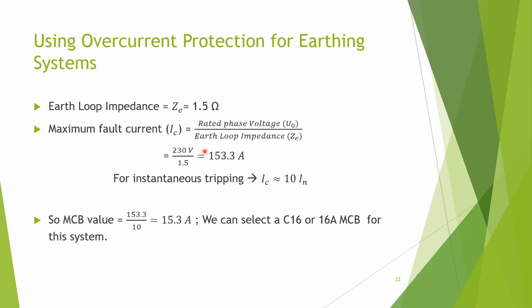And so in this case, our current is 153.3 amperes. So to select an overcurrent protection device for earth faults, we are going to divide this value by 10. 153.3 divided by 10 is 15.3, and we are going to select a 16 ampere breaker, because 16 ampere is an available standard rated value. So that's how you are going to do it. And don't worry about this C16. It is one of the notations we use to indicate breakers. We are going to learn this; it is one of the classes of breakers, C16.